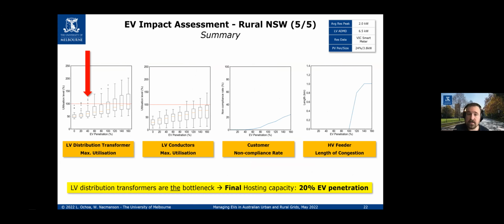So if we move to the next slide, please. We can see this now clearly when we look at the summary. So we've got the transformers on the left, the conductors, the percentage of customers with voltage issues, and the length of HV feeder congestion. So we can see very clearly that, for this feeder, we need to tackle distribution transformers to unlock that higher ability to host more EVs. So ultimately, it's all about what are the problematic assets and what limits your hosting capacity.